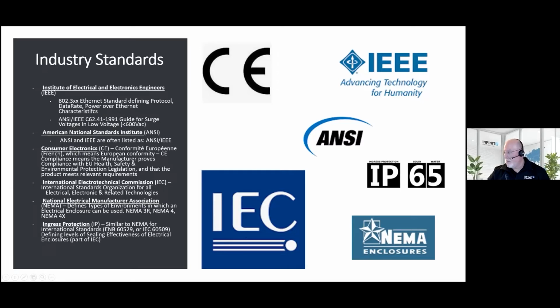The IP and NEMA ratings refer to weatherization. So if it's an outdoor related scenario, IP is usually for components and NEMA is for enclosures. So if you need it to be in an enclosure outdoors, then you'll see a NEMA rating. If it's just the surge arrestor itself, like an RF surge arrestor on a coax cable, and it's exposed to the weather, then it should have an IP 65, 67, or 68 rating. Then you know it's weatherized.